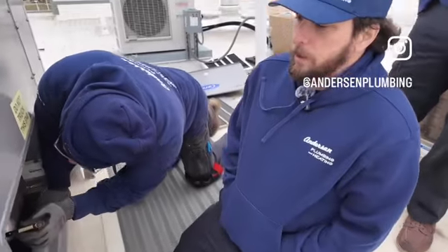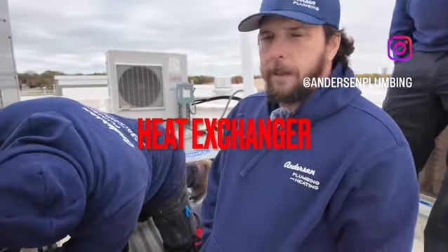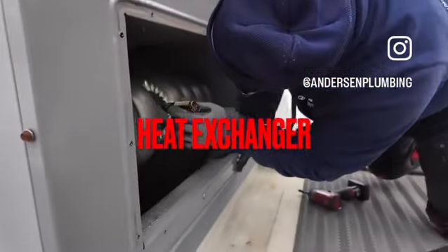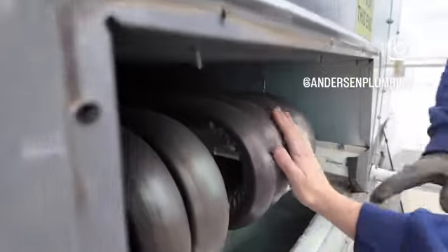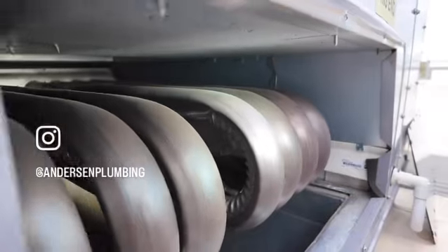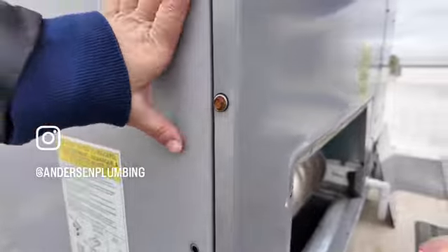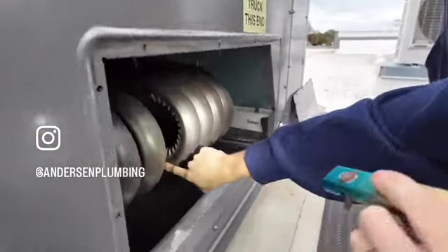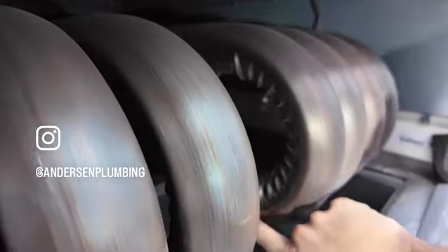Okay, so one of the other super important pieces that we inspect on these units is what's called the heat exchanger. So this is the heat exchanger that you're looking at here. This is the series of tubes. One of the things that we're looking for in the most common failure points is right on these corners where these bends are made.